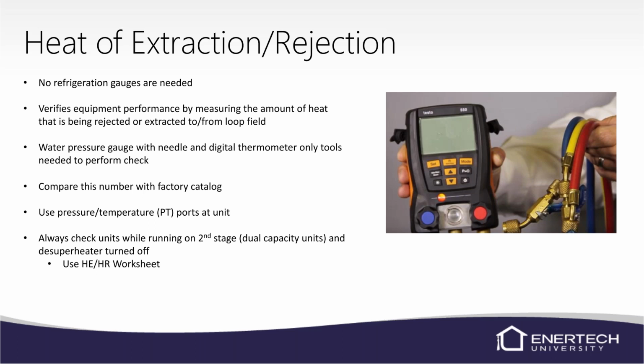A lot of our manuals do have part load information, but we would recommend second stage and turn the desuperheater off. The desuperheater will normally rob somewhere, it could be 3,000 to 5,000 BTUs. So our manuals don't normally show the information with the desuperheater running. So I'd recommend turning the desuperheater off. Or if it doesn't have a switch, you can just unplug the Molex harness for the high voltage to the pump.